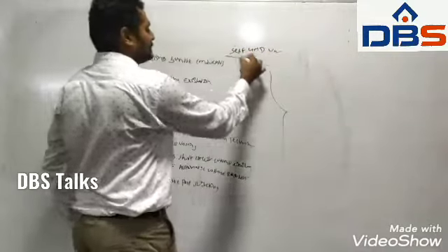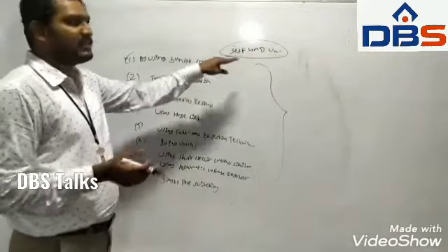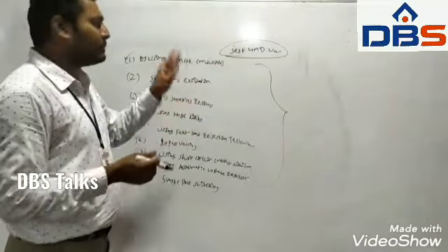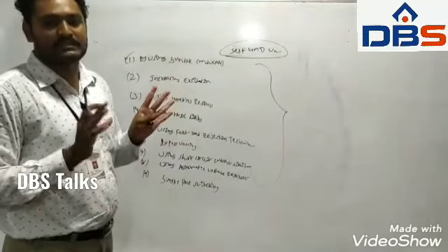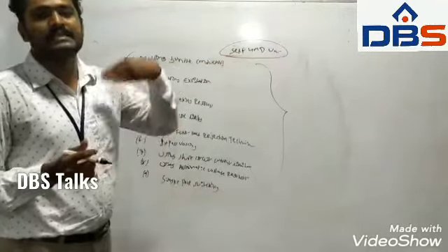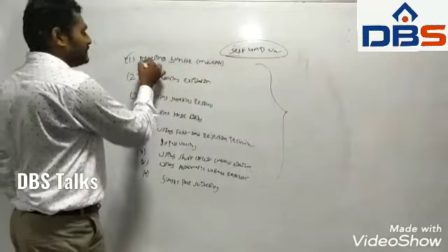By increasing the self GMD value, the inductance value decreases, and at the same time the reactance value also decreases. If the transmission network does not employ bundle conductors, there is no concept of self GMD, which means there is an increase in the inductance value and an increase in the reactance value. So that is what using bundle conductors does.